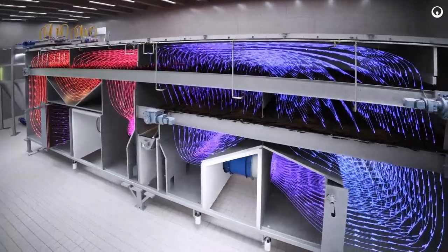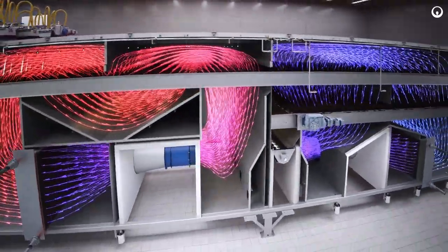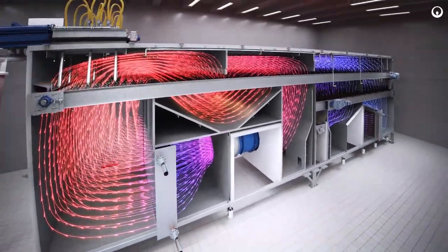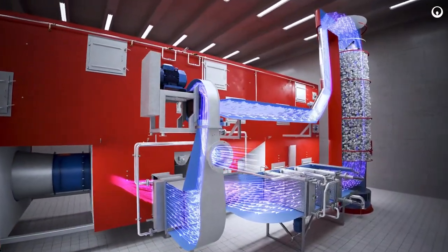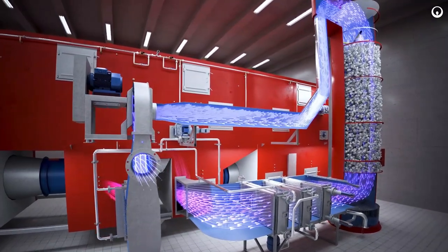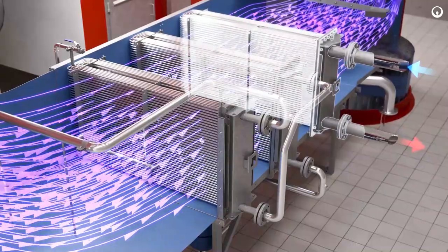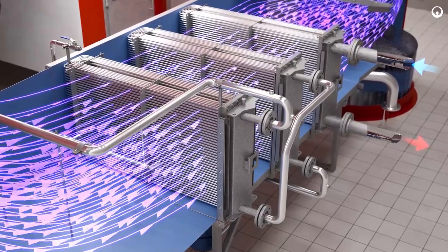This, together with the slow-moving belts, ensures an efficient sludge distribution with a large sludge surface to dry, which increases the energy efficiency of the drying process. The sludge is transported through the dryer with two stainless steel belts, and hot drying air is circulated up and down through the sludge on the belts when passing hot and cold drying zones. The water in the sludge evaporates and the wet drying air is recirculated through a condensing system with an optional Biocon Energy Exchange System (BEES). The BEES module can recover around 30% of the energy used to dry the sludge in the form of hot water.